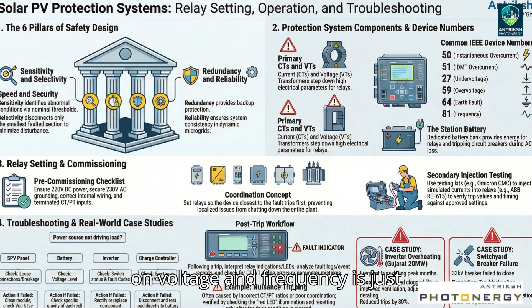Let's talk about the overcurrent relay, the 50/51. This thing is a total workhorse. Its main job is to stop your cables and equipment from literally melting. But the key is that it's smart, it knows the difference between a really dangerous short circuit, where it needs to trip instantly, that's the 50 function, and a harmless temporary overload, like when a big motor kicks on.